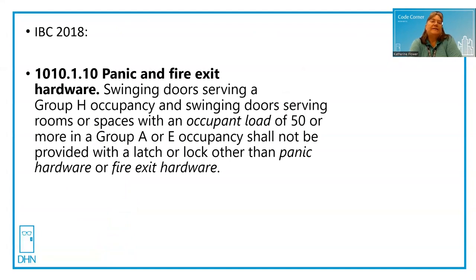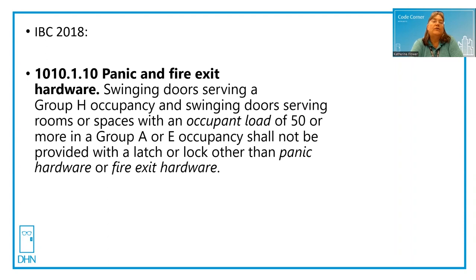This is from IBC 2018, and it's very different from NFPA 101, the Life Safety Code. Every state in the United States has adopted one version of the IBC or another. But if you do any work with healthcare, or in the state of Louisiana or Georgia where NFPA 101 is also used, or even in schools and government-type projects, you need to be familiar with the difference between IBC language and NFPA 101.